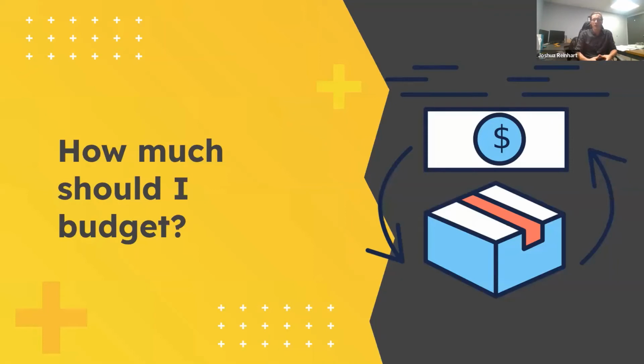And that can be pretty affordable. It can start around $700 - you're paying someone to come in and change something out mostly. As you start to require a service upgrade though, you really need to start to allocate a bit more capital to the project, especially if it's an underground service. You might even need to go up by an order of magnitude on that and start to budget into the $7,000 range, depending on what's required. It is a case-by-case basis, depending on where your electrical meter is, if there's a disconnect, if you have an overhead service or an underground service, some of those things we've already reviewed a little bit.